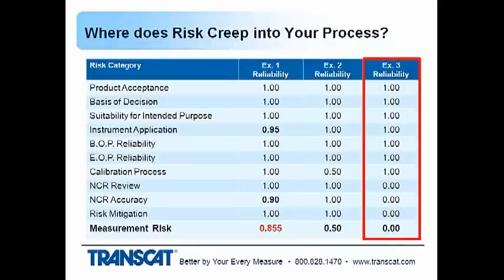Example 3, reliability would say that you don't have an NCR review process at all. I've seen situations like this, although it's not very common. But that's the point of the whole traceability chain of measurement: not only to make sure that you have equipment that's suitable for the intended purpose, but to make sure that you're using the end result of the calibration of those instruments to determine whether you have an impact to the product. And if you're not reviewing the results of those out-of-tolerance conditions, and in some cases in-tolerance conditions that are close to the limit, then you're not doing yourself any favor. You're throwing away good money for the calibration process and the use of the instrumentation to control your process.